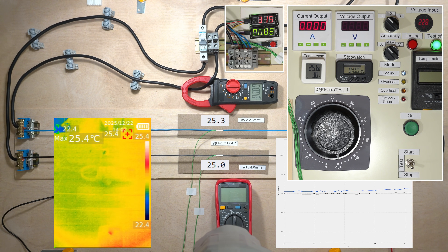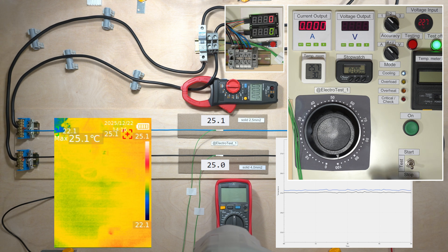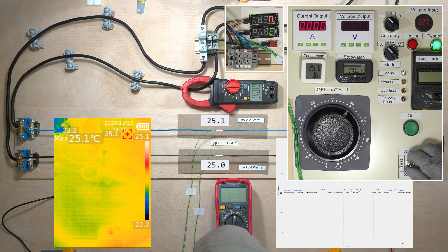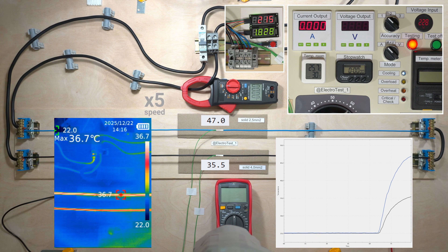With a fast shutdown at 300 amps, the wire temperature increased by only 1 degree. 200 amps lasted for 2 seconds, and the temperature rise was 40–50 degrees Celsius respectively.